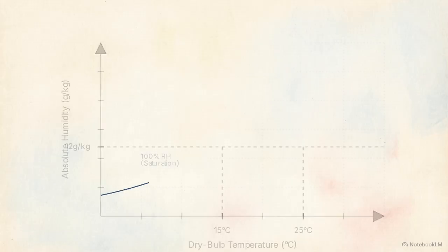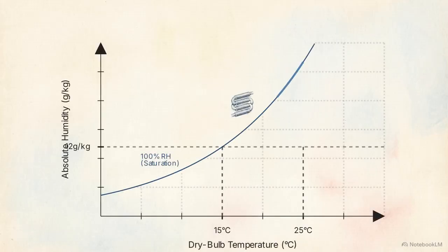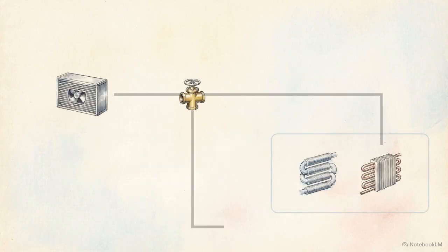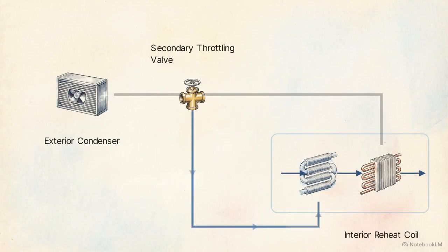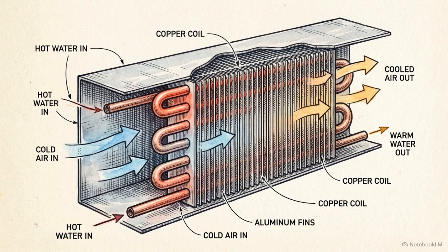Looking at this chart, decoupling requires a two-step psychrometric process: sub-dew point cooling to extract the water, followed by an immediate temperature recovery back to the comfort target. This schematic shows the first hardware configuration capable of doing this: a dedicated drying mode using a secondary throttling valve. It redirects hot refrigerant gas from the exterior condenser to an interior reheat coil. This redirected gas warms the painfully cold air back to a neutral temperature before it enters the room.